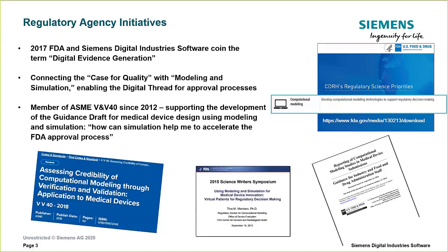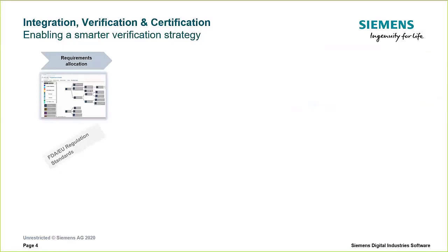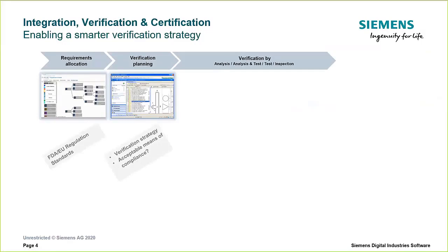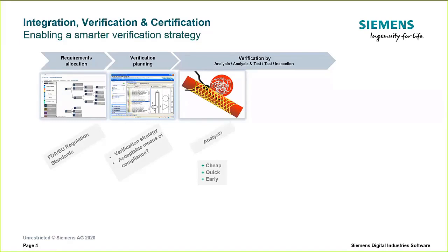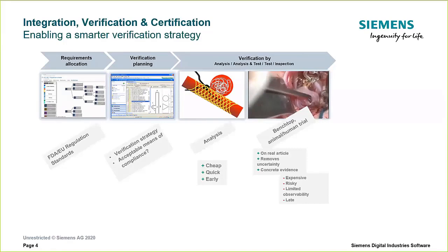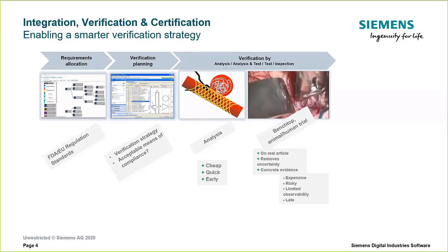In this webinar, we'll be focusing on the use of simulation for predicting product performance — that is, verification. Verification is just one stage of the medical device development cycle, which begins with requirements definition, then planning your verification strategy, followed by conducting verification activities including analysis and simulation — which are relatively cheap, quick, and can be done early in the design process — and then animal and human trials, which are more expensive with relatively limited observability and occur late in the design cycle.